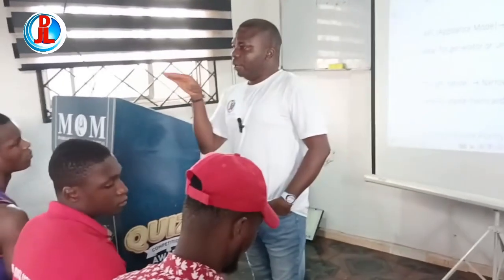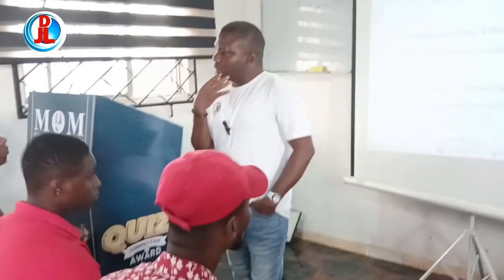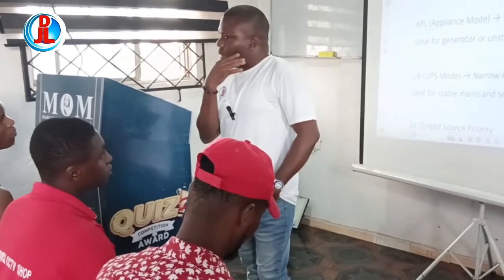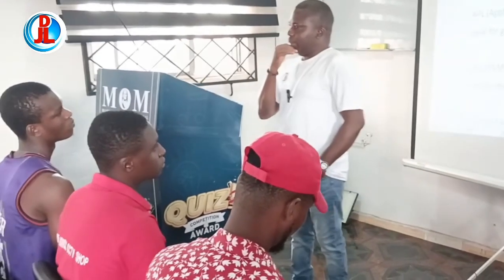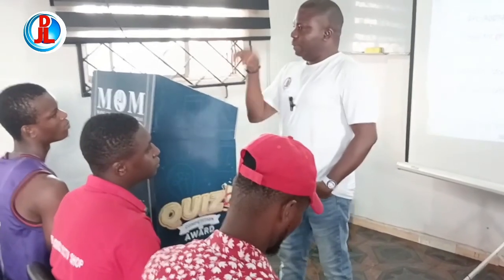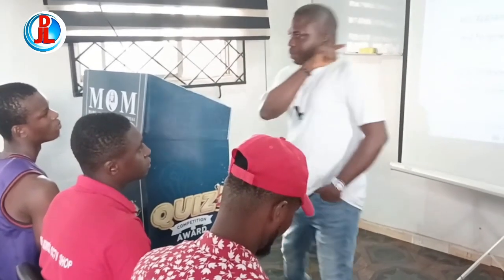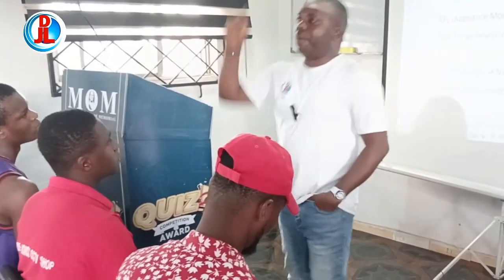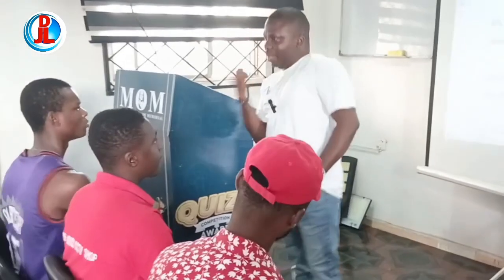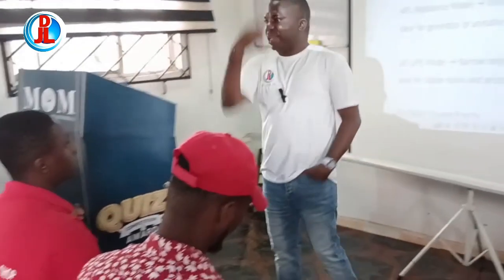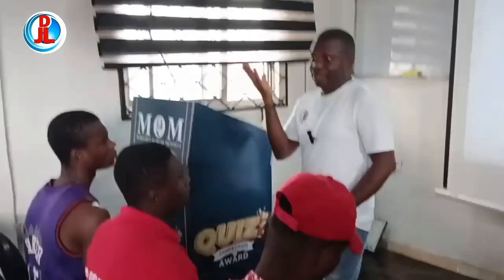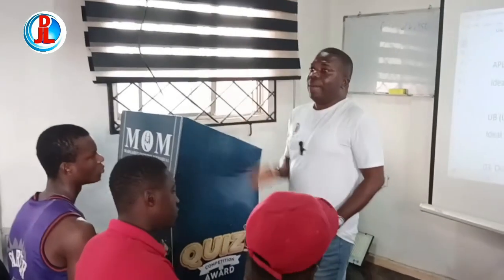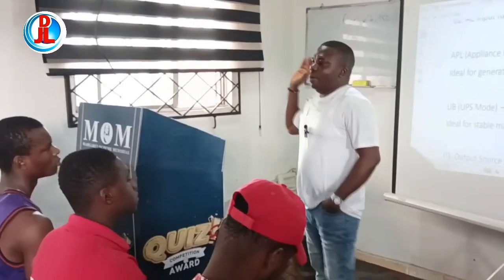Why? 170. There are some appliances that, for instance, I have an AC in this house. The AC in this house will not operate at 90 volts. Now I set my inverter to be at APL. Now NEPA brings light. If they bring light, it switches to the present voltage because the inverter does not step up voltage. It will give you what is coming in. By the time you bring out 90 volts, the AC will not work well. I don't know if you understand. By the time you give me that 90 volts, the AC will not work.